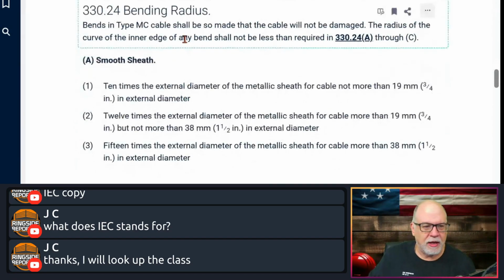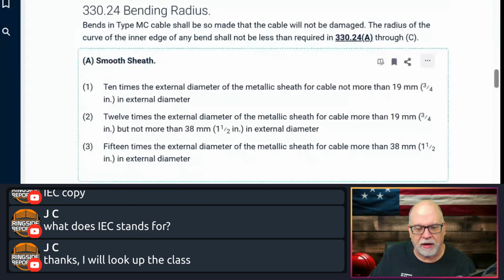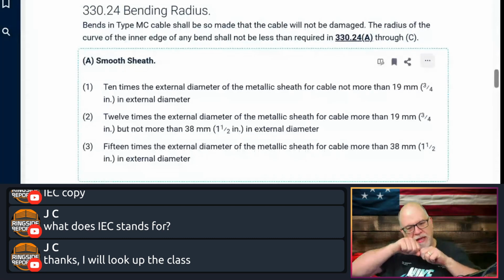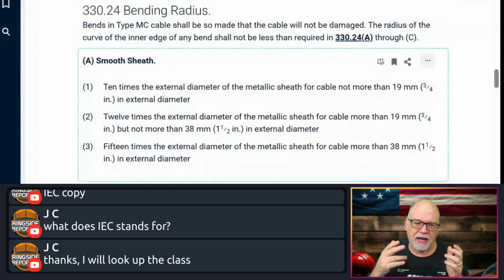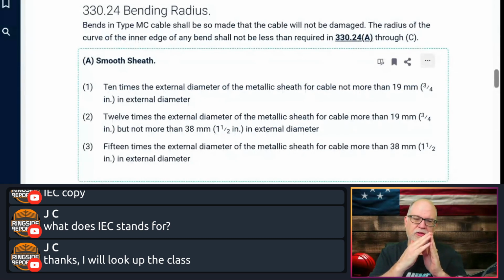Bending radius. I see people screwing this up all the time, and as a wiring cable manufacturer I get picture after picture of people that bend the MC and ask, is this okay? And then the backside of the convolution is pulled loose and exposes the conductors. No, the MC is damaged at that point. There is no market available repair for damaged MC. So you contact the manufacturer.